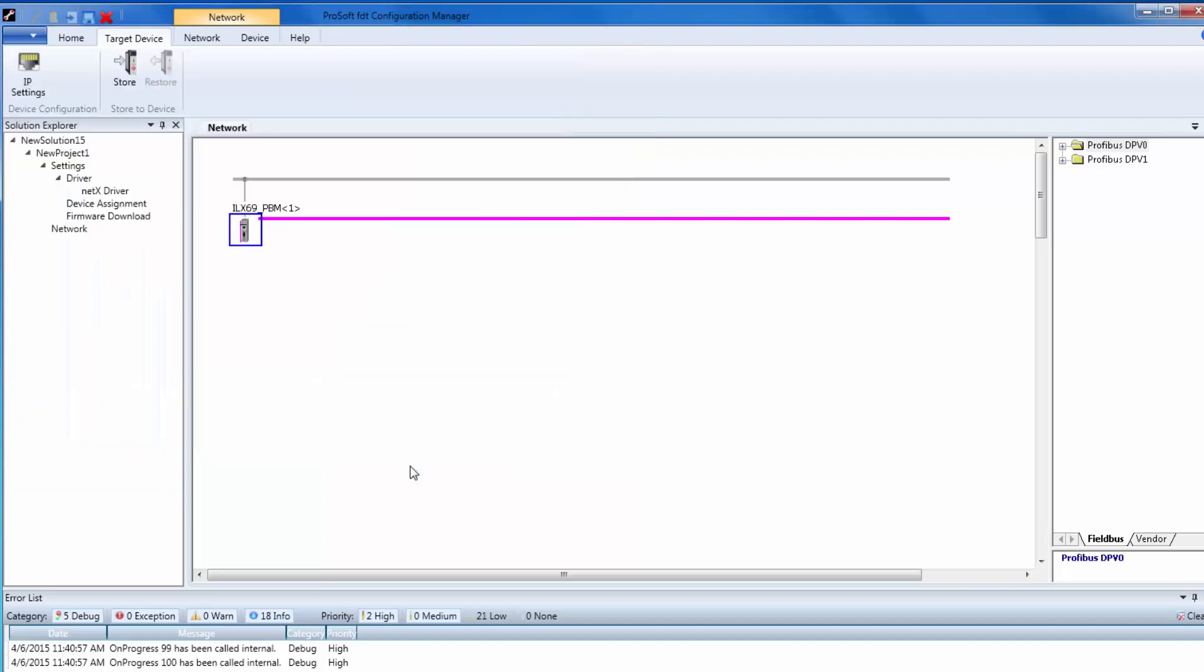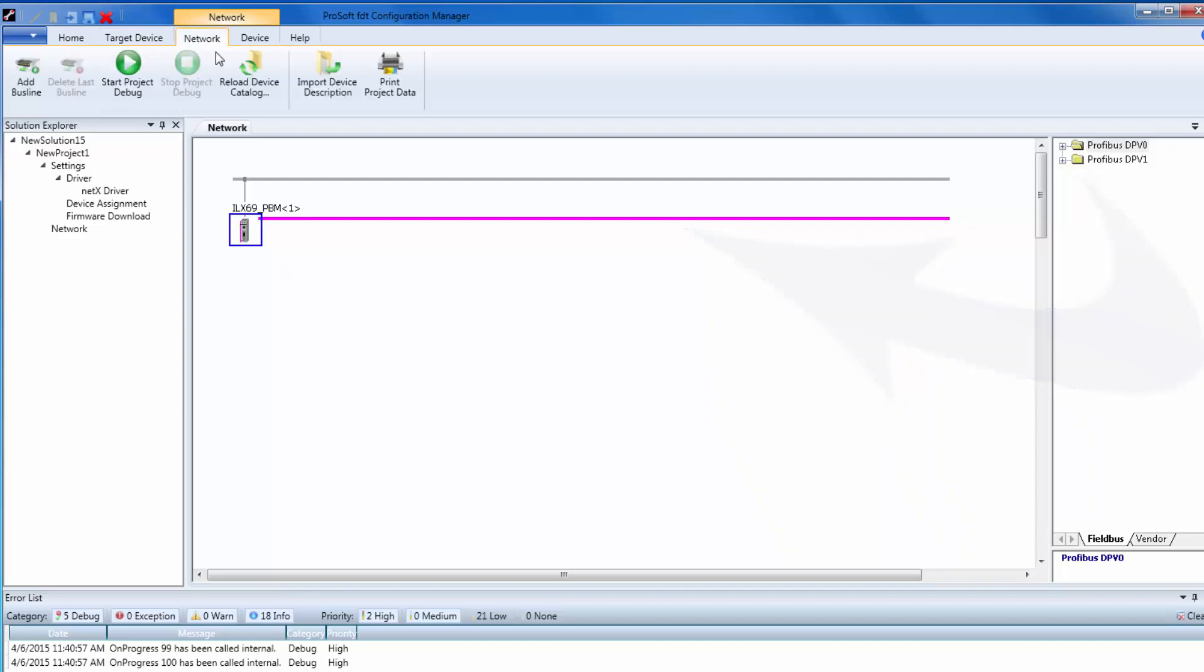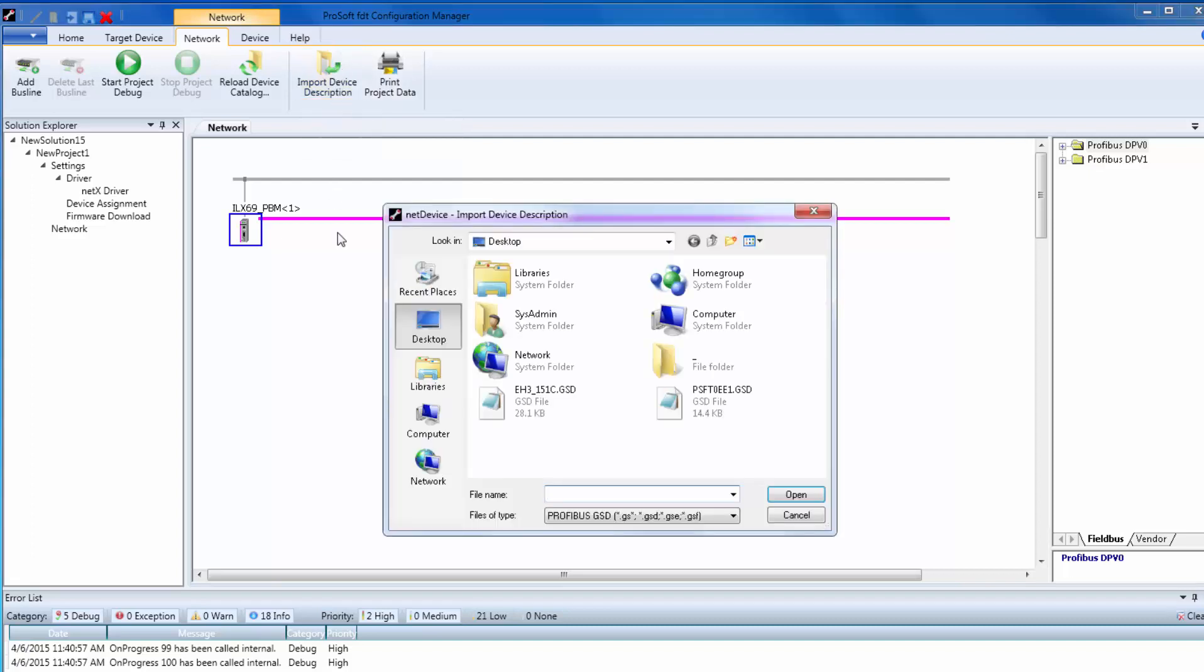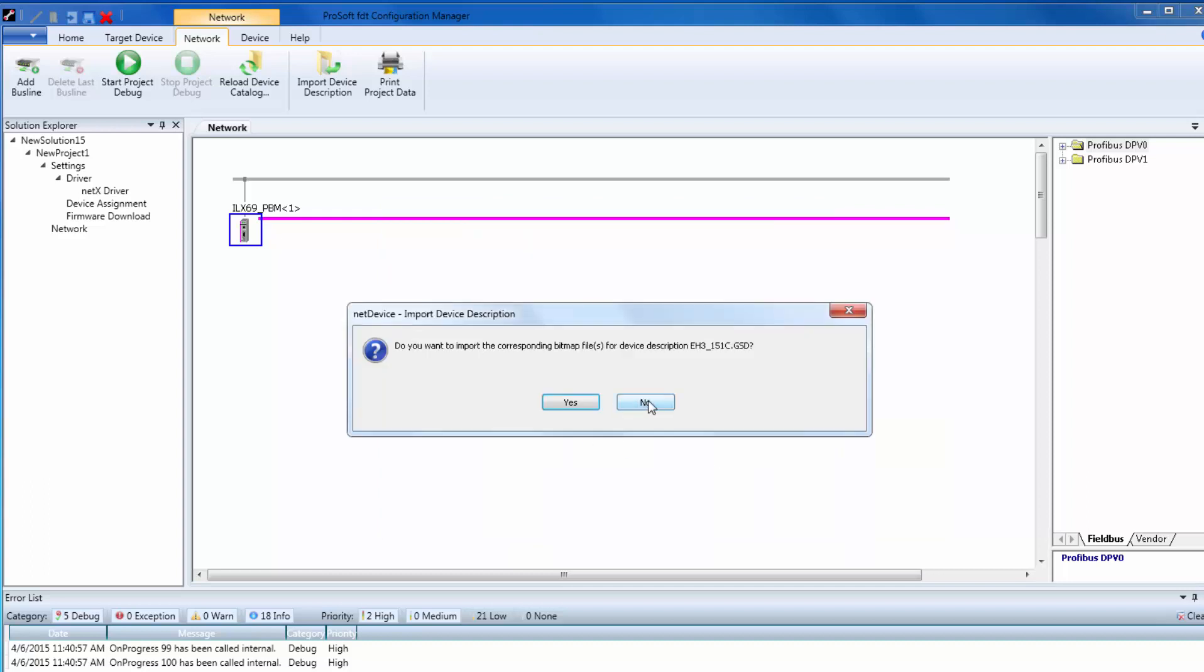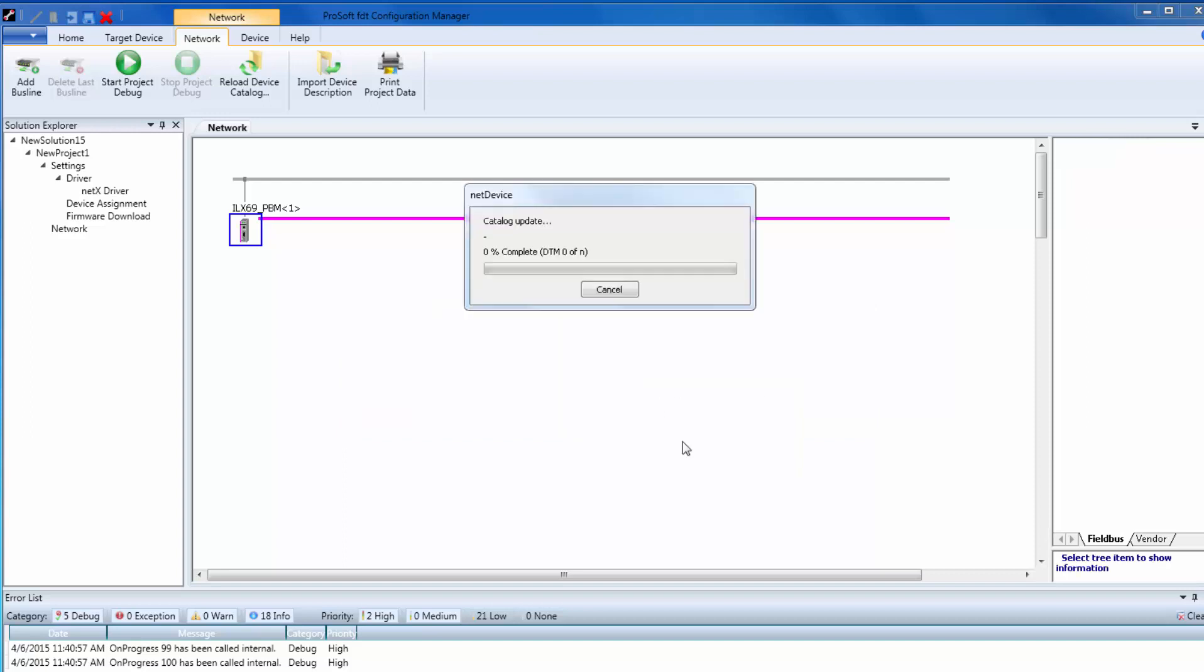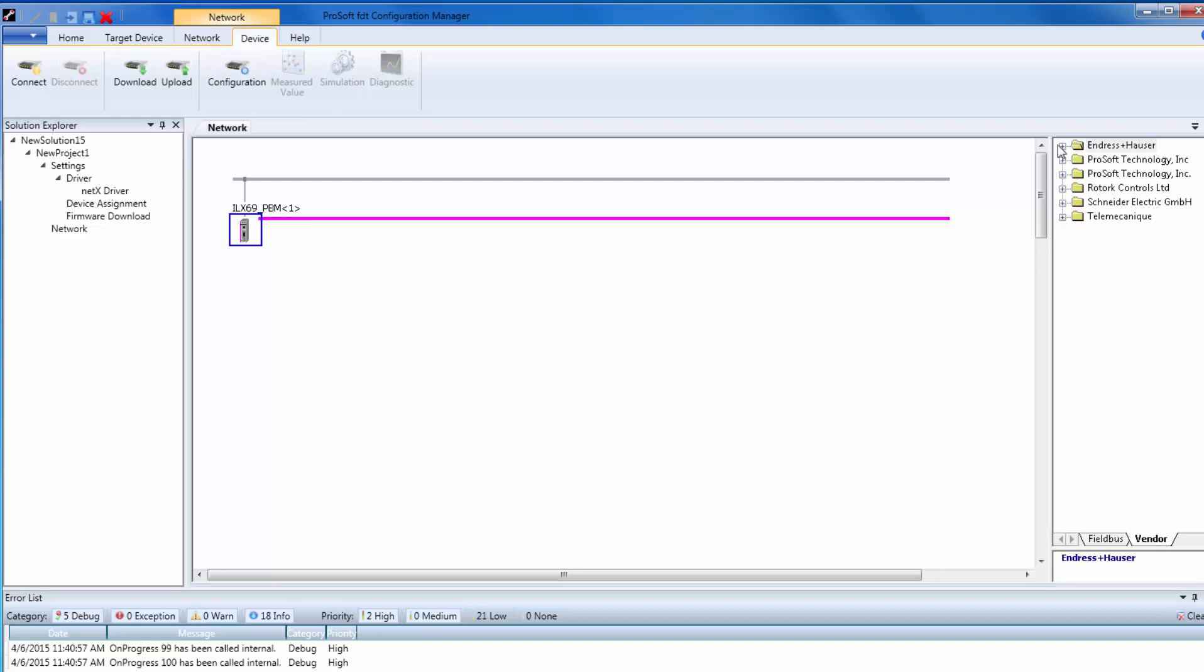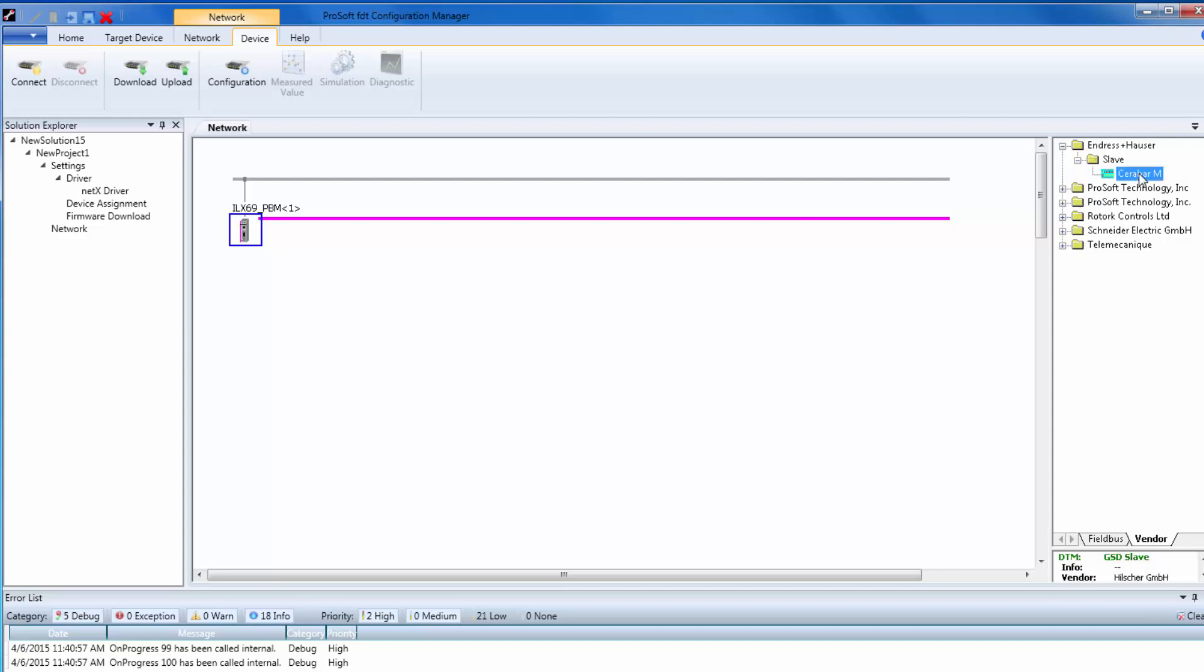Now, let's add a slave onto the Profibus network. The way to add a slave is by dragging and dropping them onto your network line from the device catalog. If you do not see your slave device in the device catalog, you need to add the GSD by clicking on the Network tab, then choose Import Device Description. Choose the GSD for your device, and then click Open. Follow the prompts until installed. Your slave will then show up in the device catalog on the right. I prefer the Vendor view to find my devices quicker.